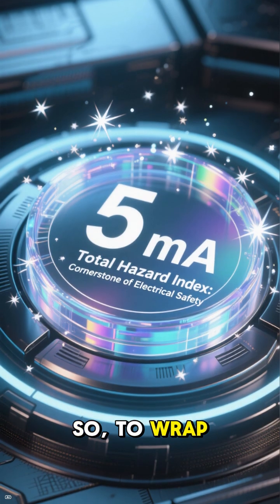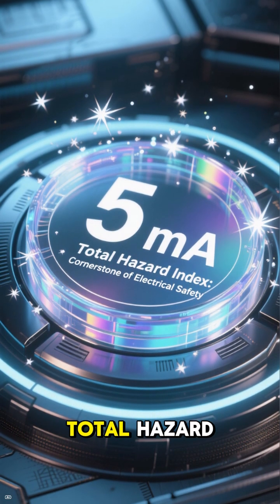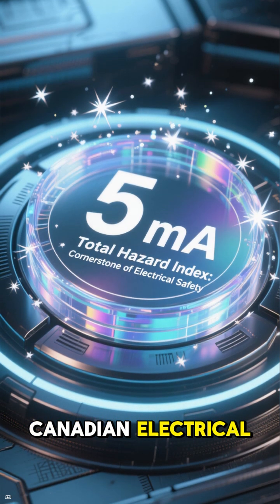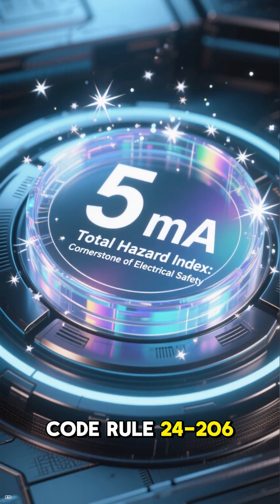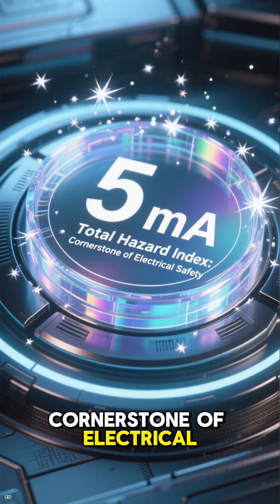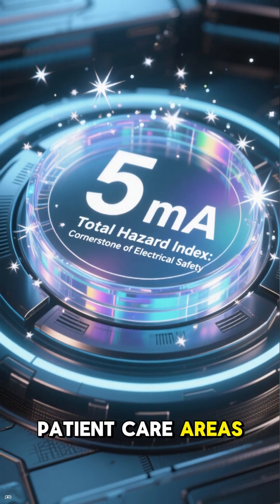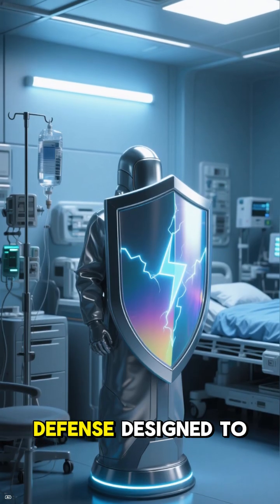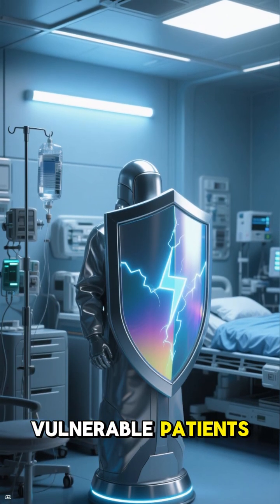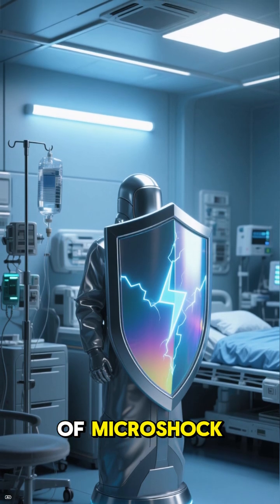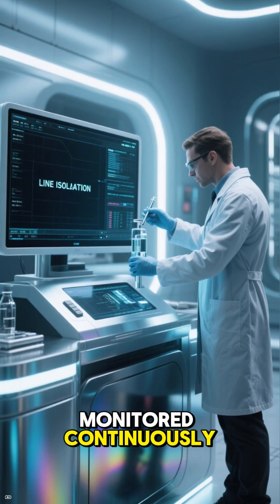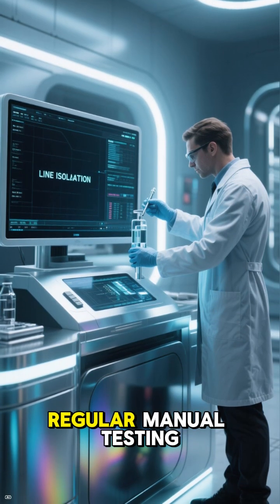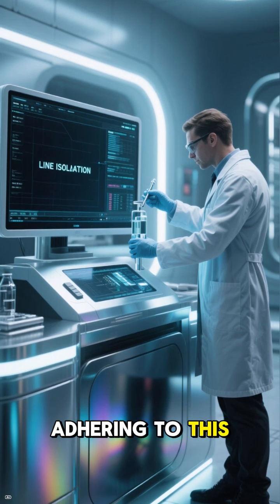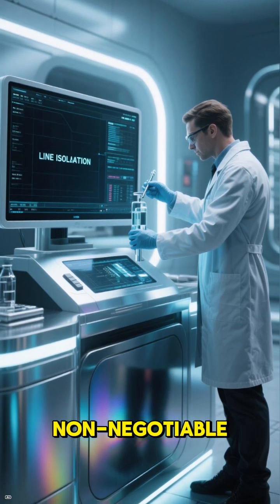So, to wrap things up, the 5 mA total hazard index limit in Canadian Electrical Code Rule 24-206 is a cornerstone of electrical safety in critical patient care areas. It's a system-level defense designed to protect the most vulnerable patients from the risk of microshock. Whether it's monitored continuously by a LIM or verified through regular manual testing, adhering to this limit is non-negotiable.